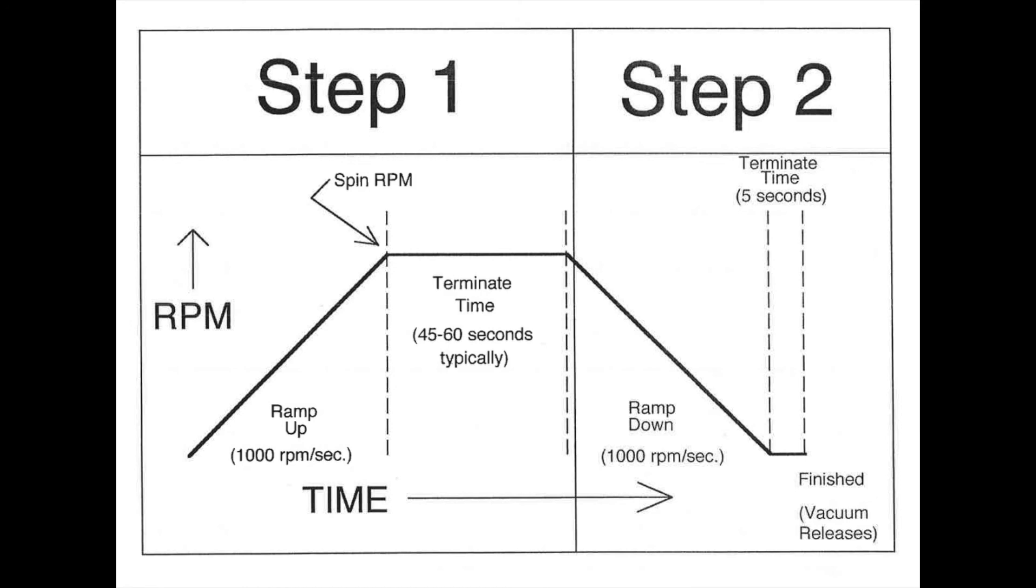Please don't mess with any of the other function or system parameter keys. These are for changing things like when it applies vacuum to the chuck, etc. You should know that for any resist, the resist spins out thinner as the spin speed is increased.